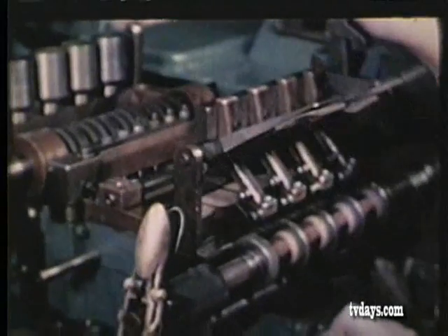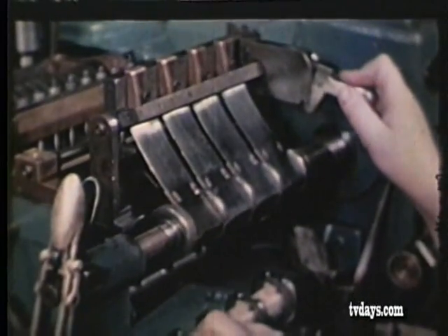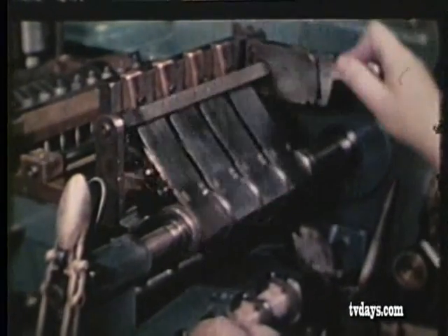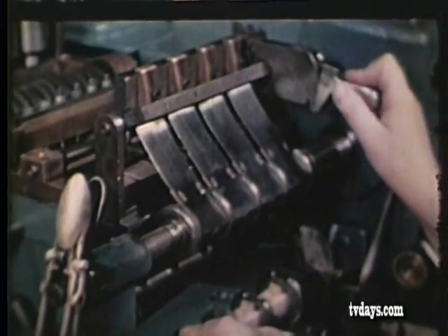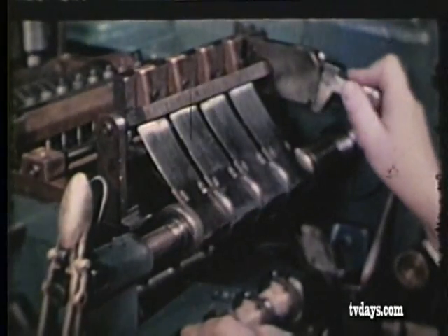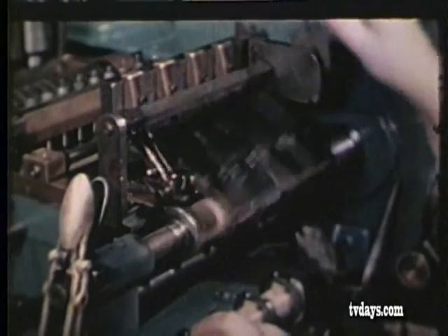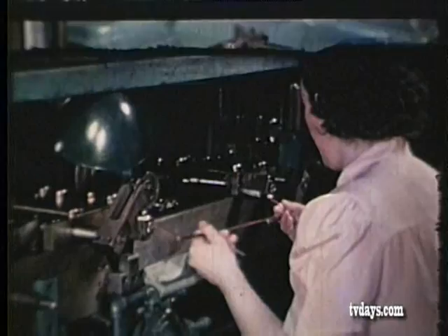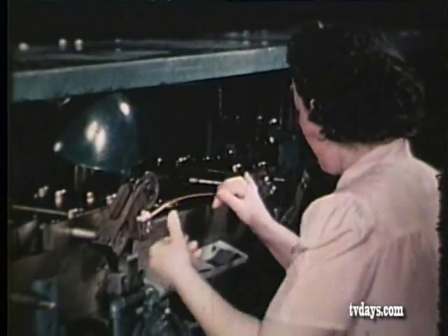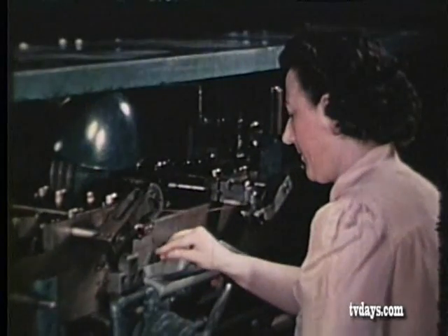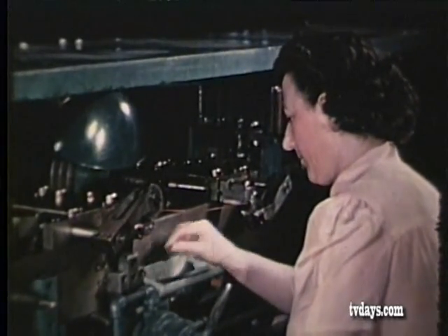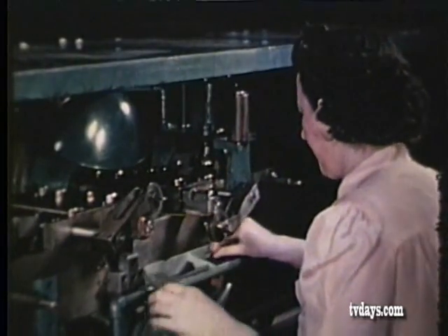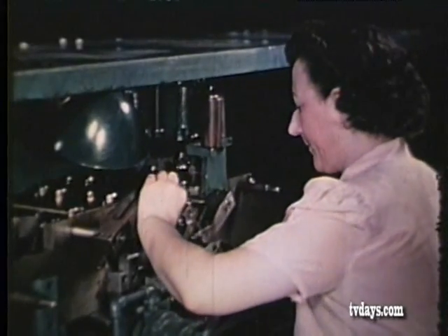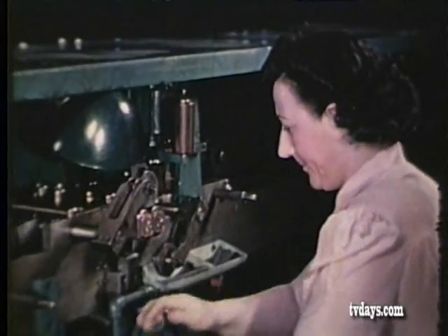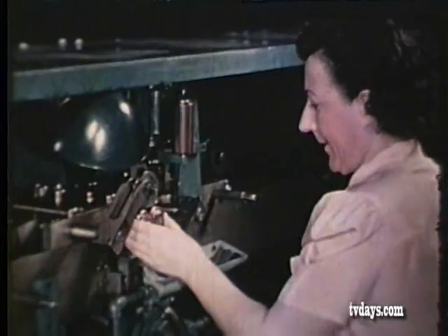Another important part of the element is the potential coil, which is layer wound to give minimum potential difference between turns. Notice how the machine automatically places insulation between each layer. The length of the paper layer insulation automatically increases as the coil grows. The current coil is wound of heavy rectangular Formex wire, both ends toward the center, with shellacked insulating strips deftly placed, first one side, then the other, and there's the current coil.